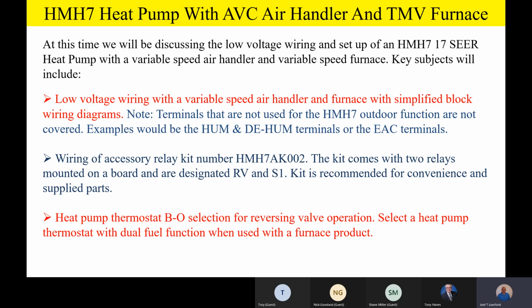Now, the burning question. Well, gee whiz, Joel, I can't get the 002 kit. They're out, and we need to hook these units up. What do I do? Take 2 peanut relays. Just take 2 common little relays with 24-volt coils, single pole, double throw relays, and your own biflow filter dryer. Now, remember, if you make up your own kit, you're going to have to field fabricate some wires, with some spade connectors on them, some low voltage wires down to the ECM motor and all that kind of stuff. But in a pinch or in a bind, the contractor can still put these in with just a couple peanut relays and his own biflow filter dryer. And so by all means, we recommend the kit for convenience and supplied parts, but you're not stuck with having to have this kit to install them. All you need is a couple relays, 24-volt coil, and a biflow filter dryer.